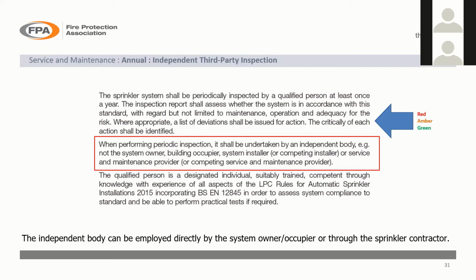And if it's something that's obviously there that should comply with the system, but probably isn't going to make the system fail, say for example some missing hydraulic notices or some missing block plan or something like that, we might sort of flag that up as a green and say, look, you should really have this, try and get hold of it. It would make it better if it was there. The sign that you've got says it's a sprinkler pump room, for example, but it's not clear where the valve sets are done. We kind of flag that up as green.